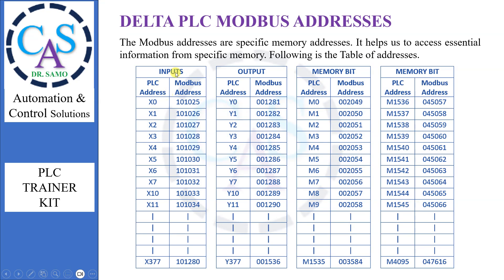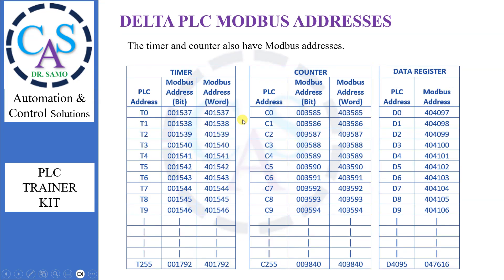Delta PLC Modbus Addresses: The Modbus addresses are specific memory addresses. They help us to access essential information from specific memory. The following is the table of addresses. PLC addresses and Modbus addresses are given. Input pin has PLC Address X0 and Modbus Address 101025. Output pin has PLC Address Y0 and Modbus Address 001281. Memory M0 has PLC Address M0 and Modbus Address 002049. We always use Modbus addresses in Modbus Protocol RS-485 communication. Timers and counters also have Modbus addresses.